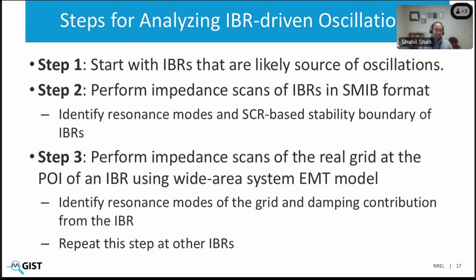So let's see what we require to do these 3 steps. For step 1, which is basically for post-event diagnostics, you really need field measurements. For step 2, you need only IBR models. You don't really need system models. And for step 3, you require both IBR models and system models. So as a system operator or owner, there are certain insights that you can achieve just by doing steps 1 and 2. Step 3 is something which will give you concrete or exact answers, but then you need to have a system EMT model.